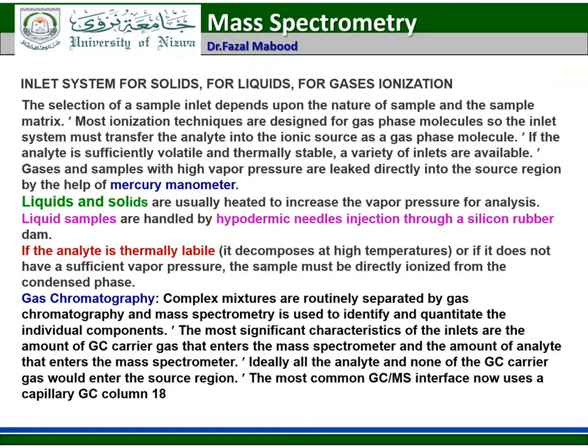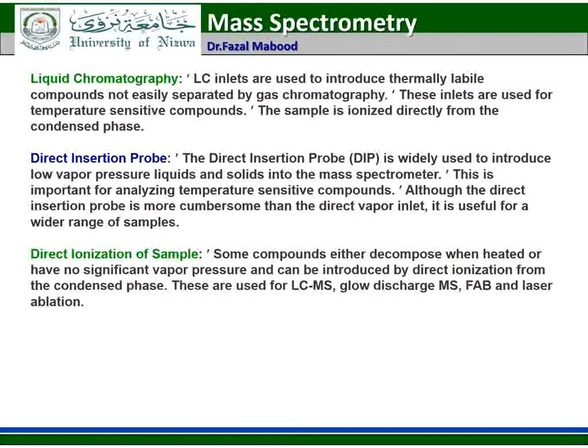Liquid chromatography inlets are used to introduce thermally labile compounds that cannot easily be separated by gas chromatography; these inlets are used for temperature-sensitive compounds where the sample is ionized directly from the condensed phase. The direct insertion probe is widely used to introduce low vapor pressure liquids and solids into the mass spectrometer, important for analyzing temperature-sensitive compounds. Some compounds either decompose when heated or have no significant vapor pressure and can be introduced by direct ionization from the condensed phase, used in LC-MS, glow discharge MS, FAB, and laser ablation.